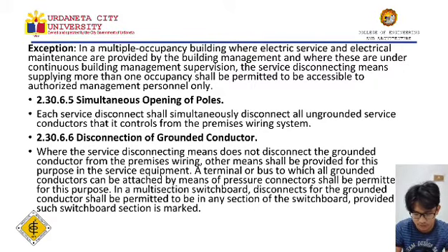Disconnection of grounded conductor. Where the service disconnecting means does not disconnect the grounded conductor from the premises wiring, other means shall be provided for this purpose in the service equipment. A terminal or a bus to which all grounded conductors can be attached by means of pressure connectors should be permitted for this purpose. In a multi-section switchboard, disconnects for the conductor should be permitted to be in any section of the switchboard, provided such switchboard section is marked.